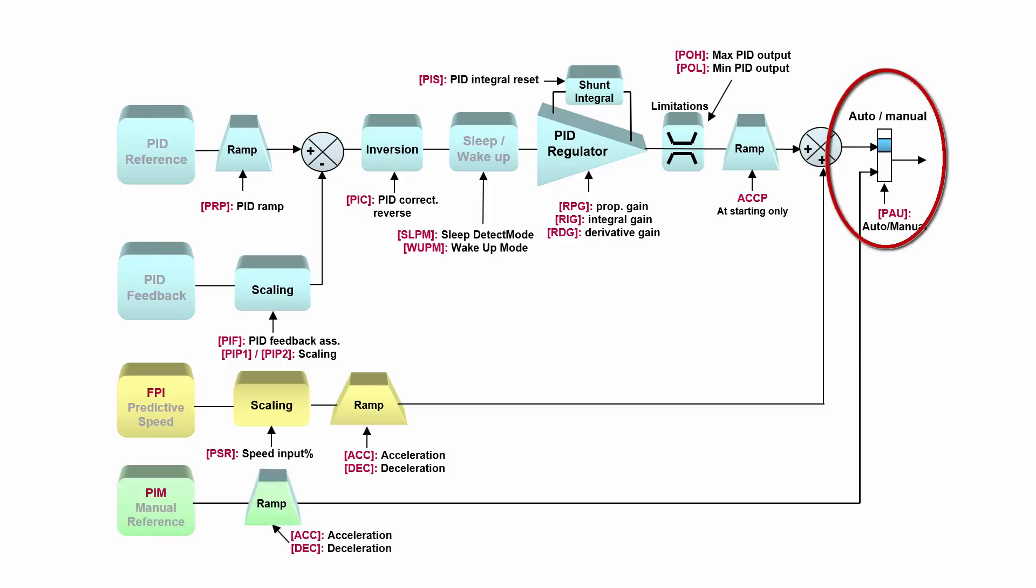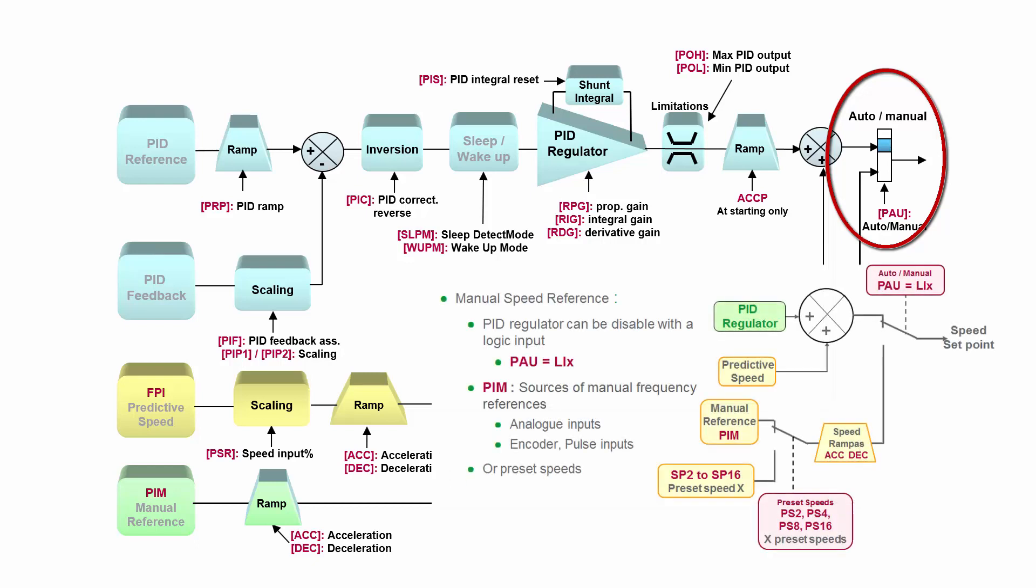So one important thing to say: this is not disabling the PID regulator, but this is only switching the output of PID regulator to speed setpoint. When you are in manual mode, PID regulator is still working. When you switch back to auto, PID regulator takes the control of the drive.